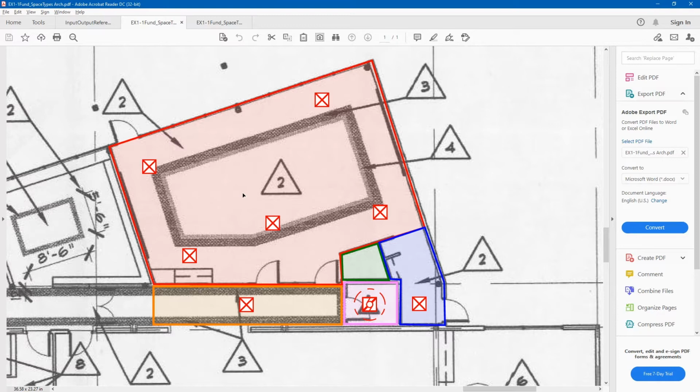So what I have done is I've broken these up into a little bit more numerous thermal zones. I've assigned this hallway to its own thermal zone because it's got its own supply air diffuser here. I've assigned this entryway to its own thermal zone. It's got its own supply diffuser, and it might be important to keep track of the heat flow through this corner of the space. The restroom has its own thermal zone because it's got an exhaust fan. And then there's a conference space and this storage area.